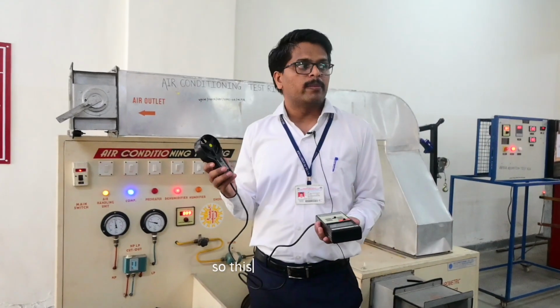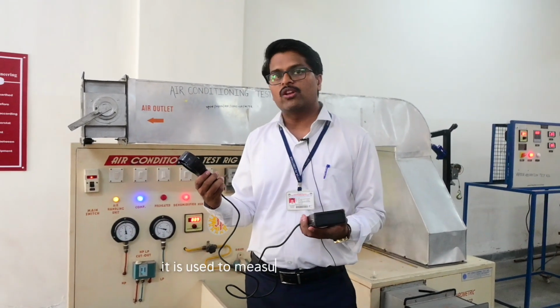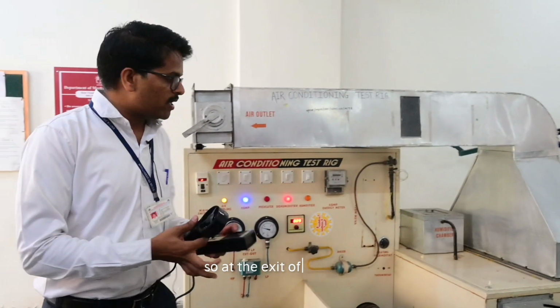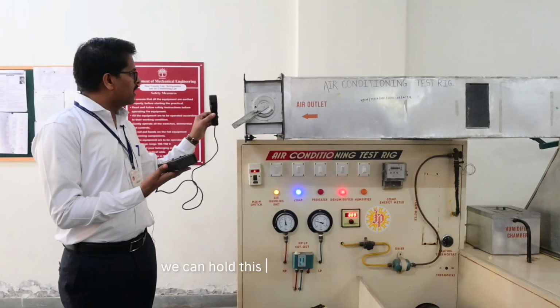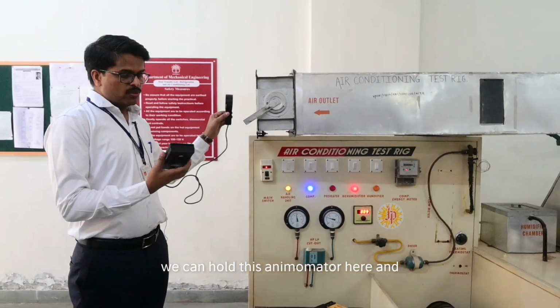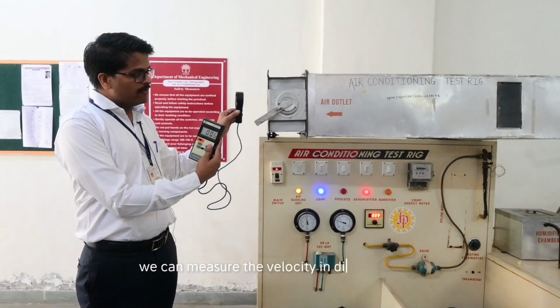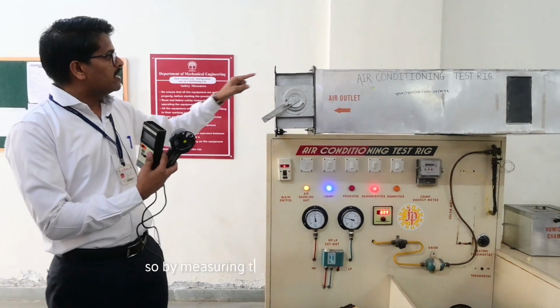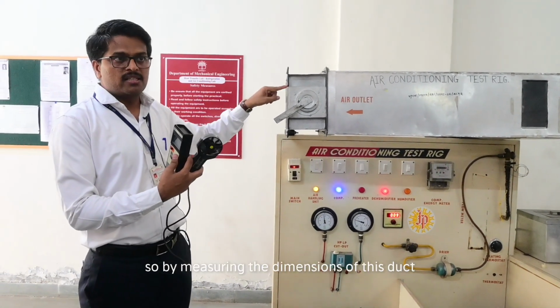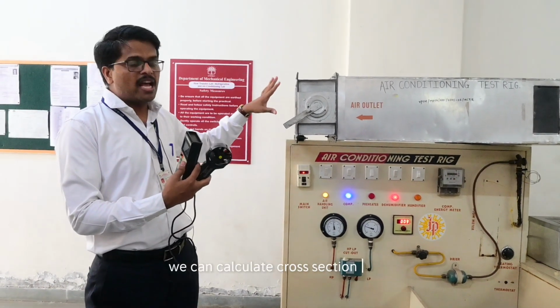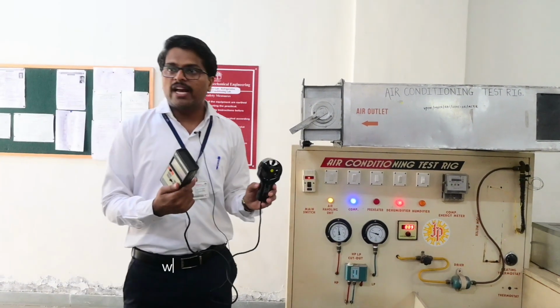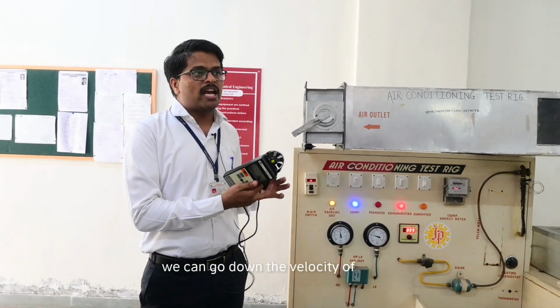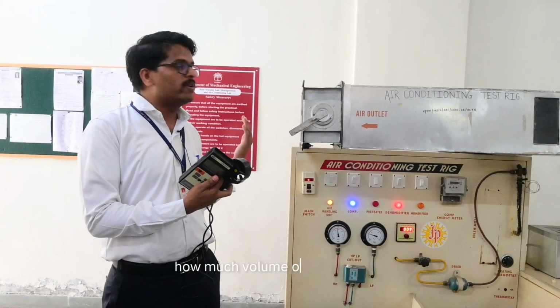So this is the anemometer. It is used to measure the velocity of air. So at the exit of the duct, we can hold this anemometer here and we can measure the velocity in different units. By measuring the dimensions of this duct, we can calculate the cross section area, and by using this anemometer we can note down the velocity of the air and we can calculate how much volume of air is flowing.